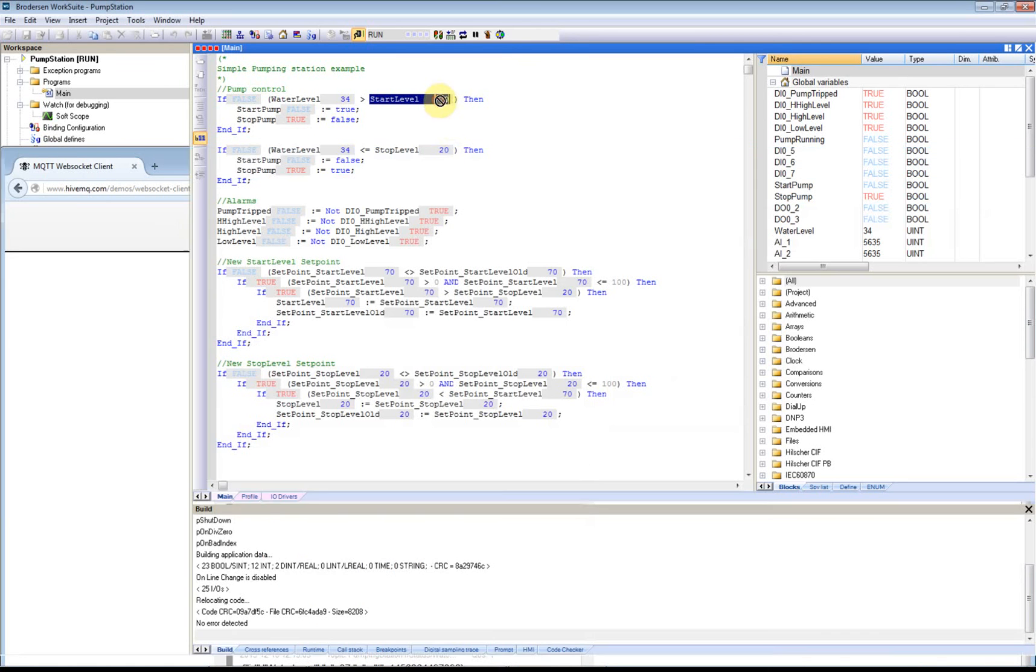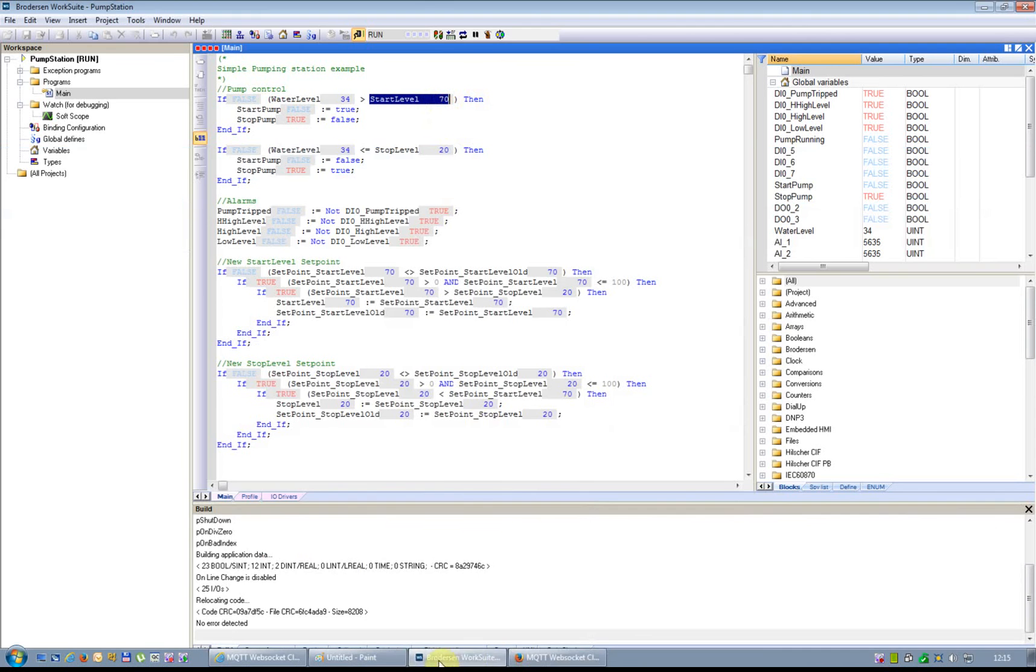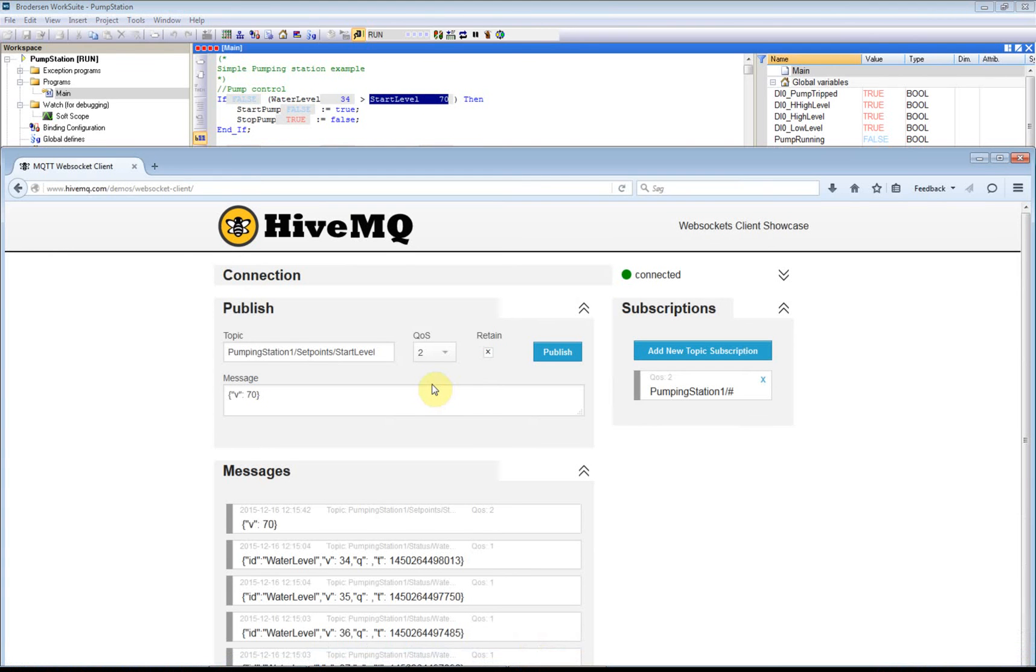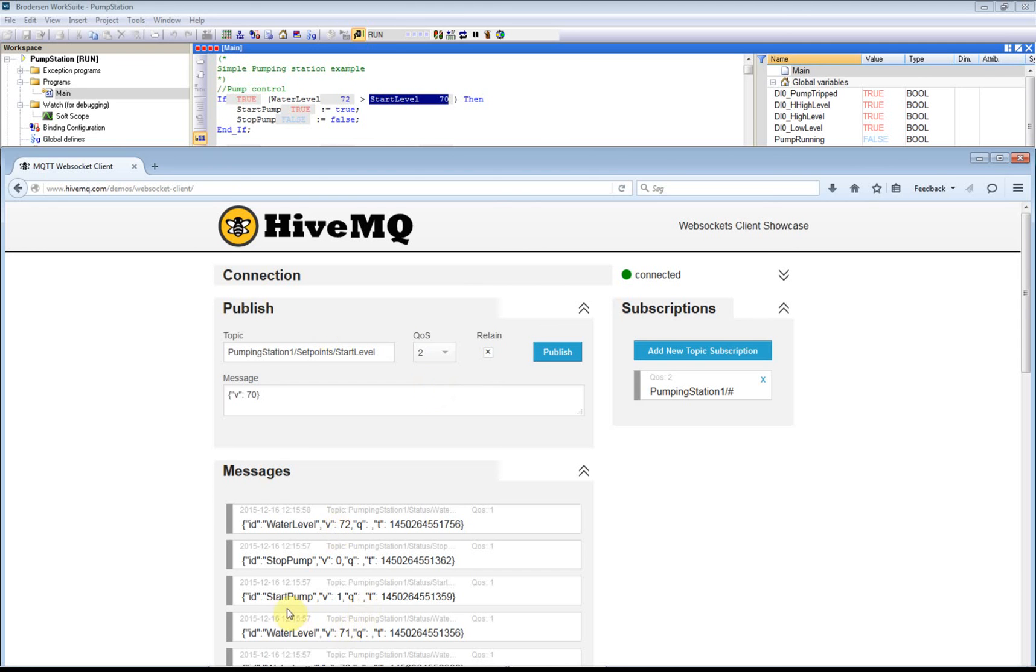And it now changes to 70. So we can see here now the pump should start when the water level is above 70. You can see here now we have the event start pump which is now 1, and stop pump is 0. So this was all for now. Thank you for watching this small video demonstration.